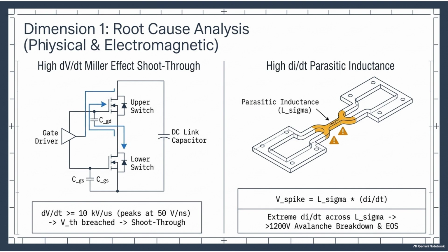And the voltage generated across an inductor equals that inductance multiplied by the rate of change of the current. Since the dI/dt during a short is so violent, even a microscopic amount of parasitic inductance multiplies out to a massive voltage spike. So it's a bottleneck. The current is trying to slam to a halt or change direction instantly, and the inductance of the metal itself pushes back, generating this massive pressure spike of voltage. Yes, and if the component is rated to withstand 1200 volts, and this transient spike hits 1300 or 1400 volts, the silicon is subjected to electrical overstress. The electrons are forced through the insulating layers of the chip with such kinetic energy that they physically tear the atomic lattice apart. Wow. That is the avalanche.